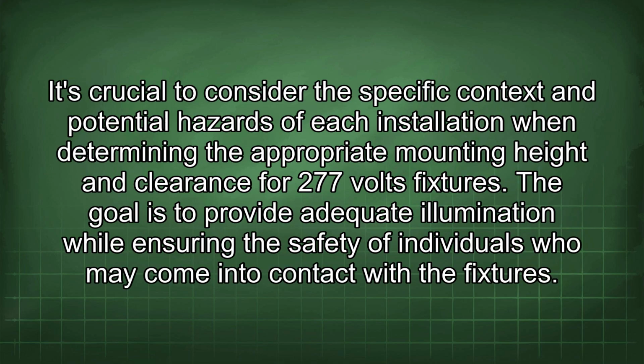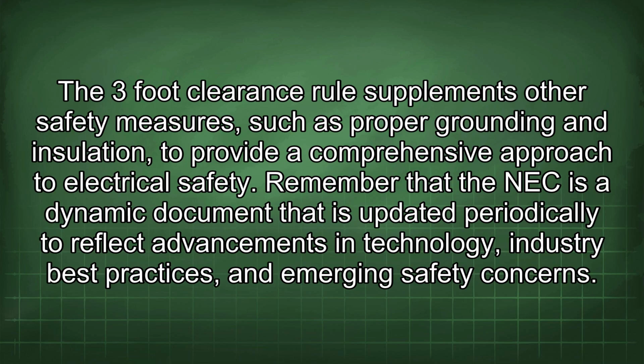It's crucial to consider the specific context and potential hazards of each installation when determining the appropriate mounting height and clearance for 277 volt fixtures. The goal is to provide adequate illumination while ensuring the safety of individuals who may come into contact with the fixtures. The 3-foot clearance rule supplements other safety measures, such as proper grounding and insulation, to provide a comprehensive approach to electrical safety. Remember that the NEC is a dynamic document that is updated periodically to reflect advancements in technology, industry best practices, and emerging safety concerns.